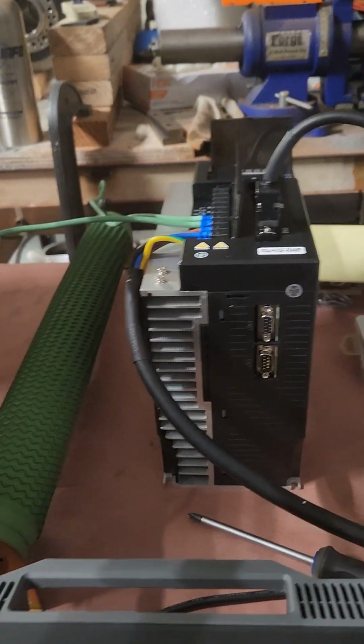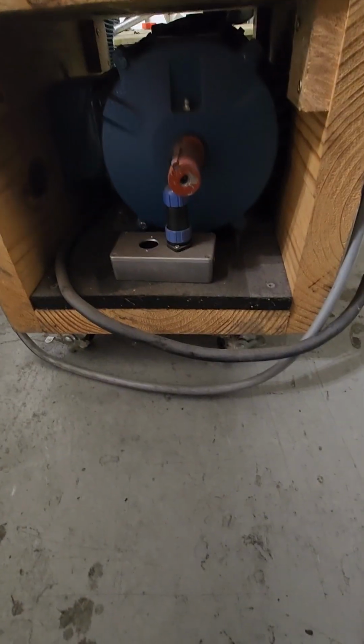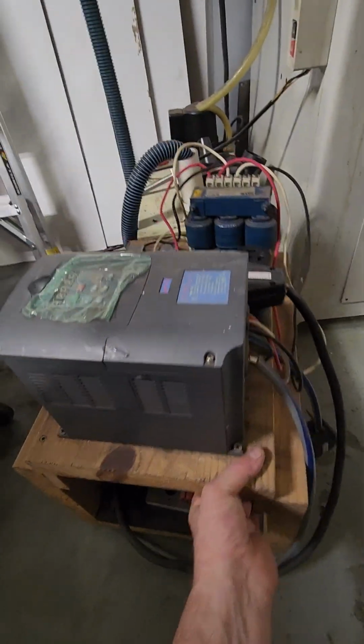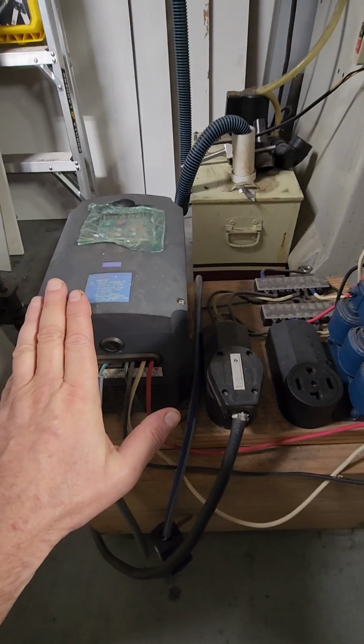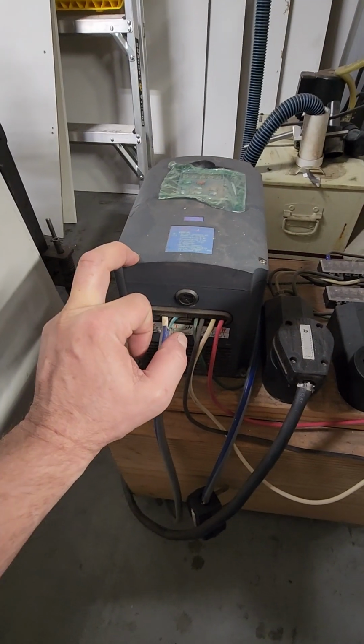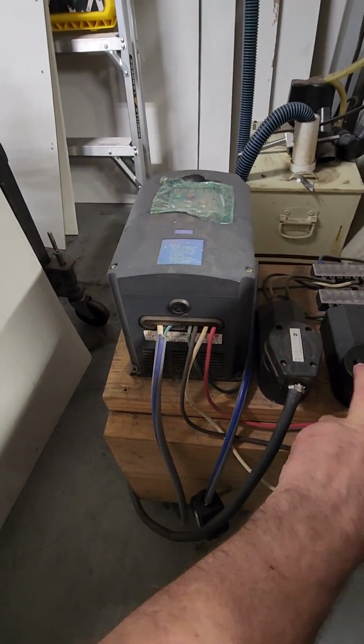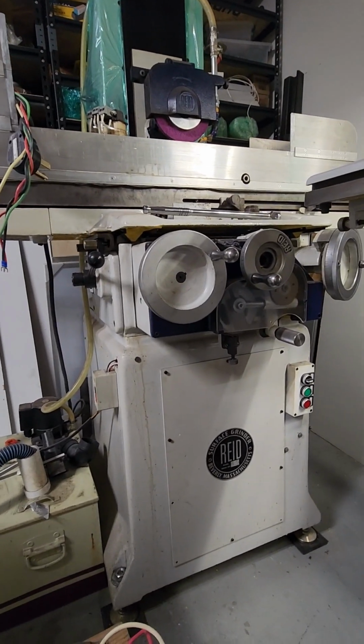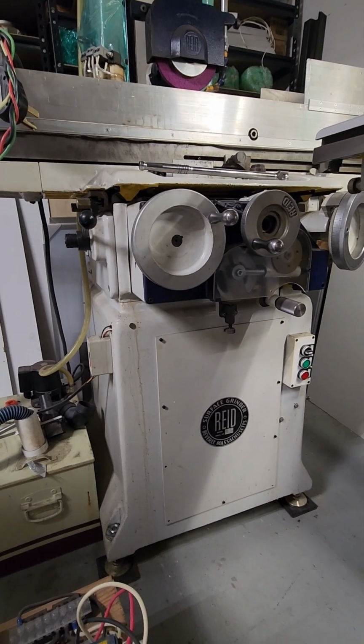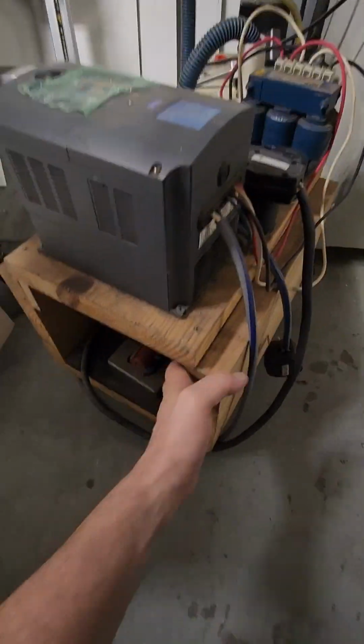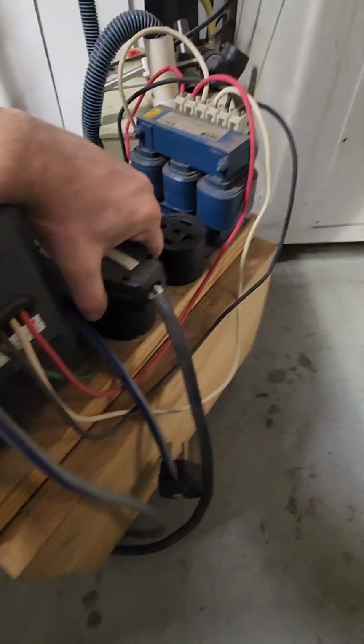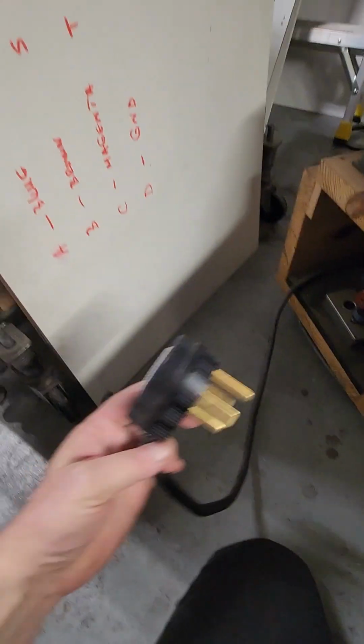I'm thinking, before putting power on this guy, I have a 5.5 kilowatt motor here. I have this 5.5 kilowatt motor. This I'm using it as sort of a filter, if you wish, because this is my three-phase 220 volts power, again from 240 volts AC. Again, I'm using an inverter, powers that motor, but that motor has no load, and then I take power from here, three-phase 220, through a line reactor, and I power my surface grinder. Has a three-phase motor, 220 volts. So I'm thinking to actually power this motor. I mean, I can disconnect it from here. Now it's isolated. I can power it, all by itself, and I can use. Let me see.